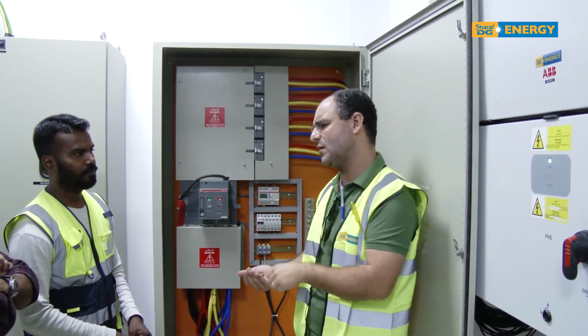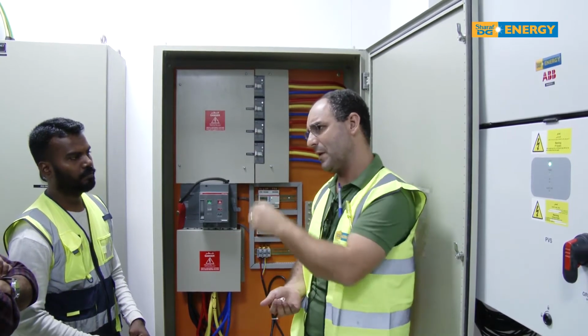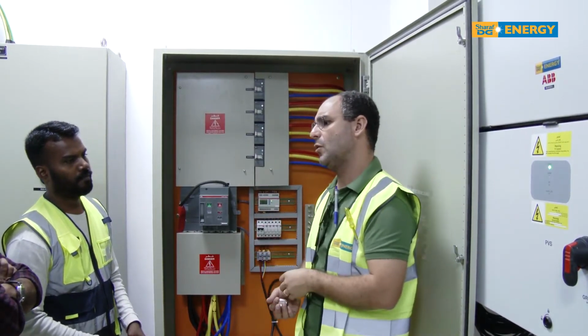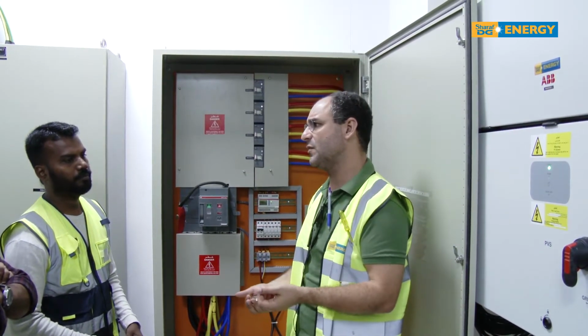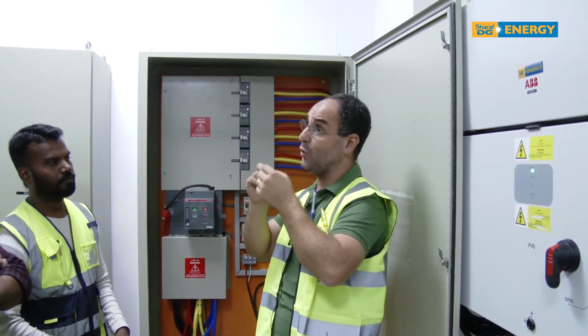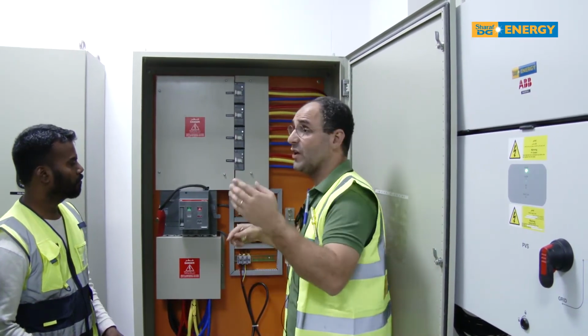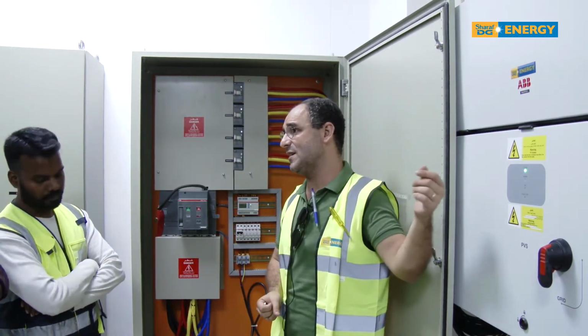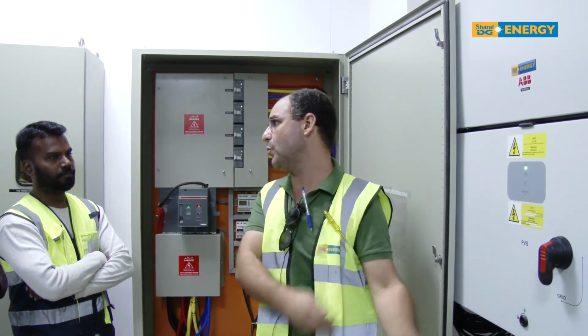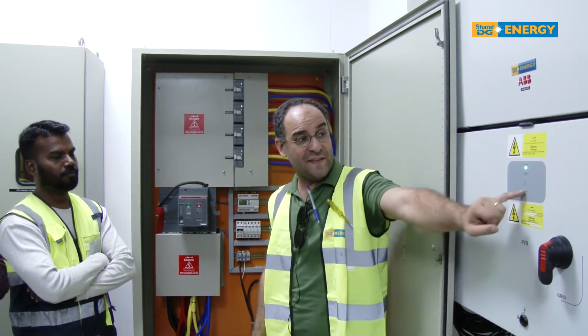And the idea is that people don't invent much. Internal setups, you can do different stuff, of course. You can play with it: lead, lag, control reactive, not control reactive, change the setup of the intervals for frequency and voltage. You can play with that. But if it is a malfunction or some hardware problem, then take the machine, put a new one under warranty. Okay? And then it says GFI. GFI means ground fault indicator.